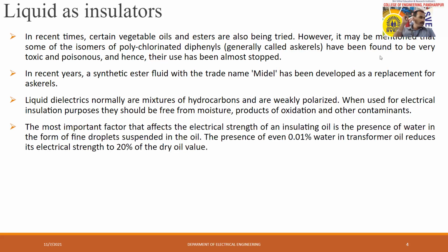An important parameter to consider is the electric strength of insulating oil. When there are some water droplets in the oil, even the presence of 0.01% water in transformer oil will reduce the electrical strength to 20% of the dry oil.